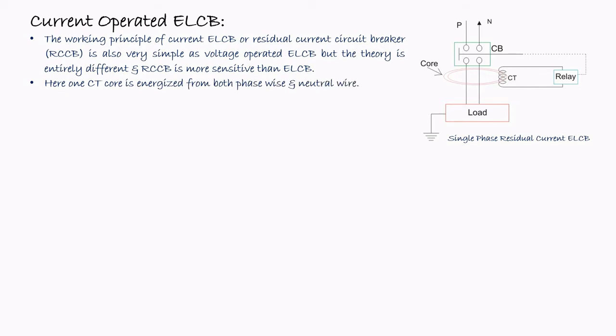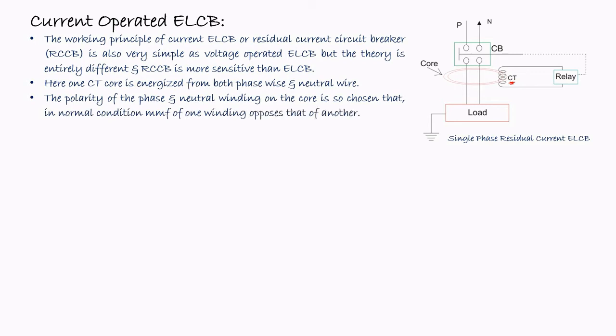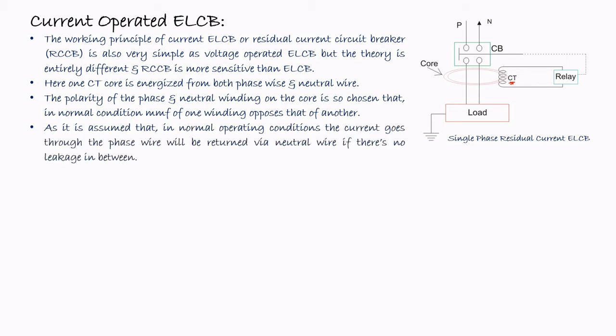Here one CT core is energized from both the phase wire and the neutral wire. So here in this figure the CT is there, that is the current transformer. The polarity of the phase and neutral windings on the core is so chosen that in normal conditions, the magnetomotive force of one winding opposes the other. It is assumed that in normal operating conditions, the current goes through the phase wire and is returned via the neutral wire if there is no leakage between them. That means the current flowing in the phase wire will be the same as the current flowing in the neutral wire in normal condition. Therefore, the magnetomotive force developed by the two wires will be equal and opposite. Now, as both currents are the same, the resultant magnetomotive force produced by these two currents is equal to zero.